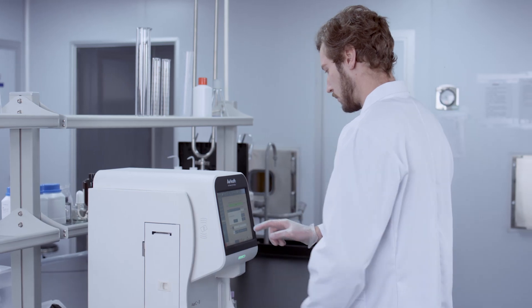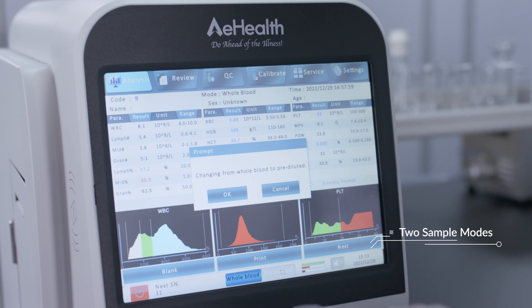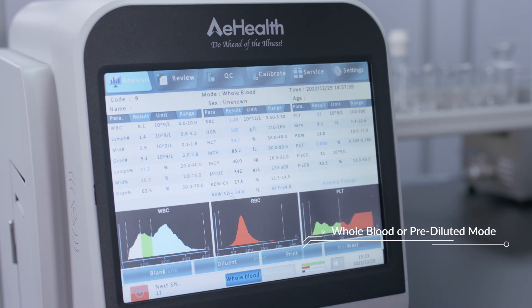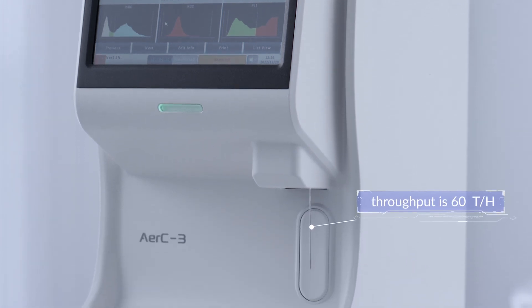The AerC-3 has two sample modes — whole-blood mode and pre-diluted mode — each distinguished by two colors to avoid misoperation. Throughput is 60 tests per hour.